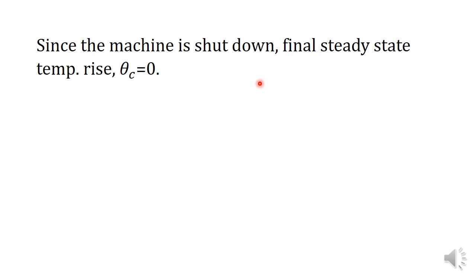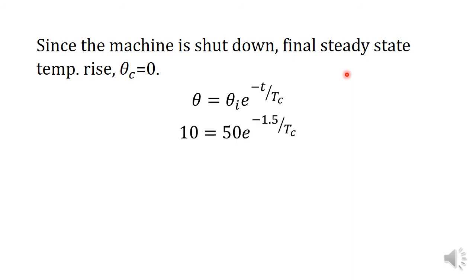Since the machine is shut down and not heated again, it is allowed to cool completely to ambient temperature, so the final steady state temperature rise theta_c equals 0. The cooling equation becomes theta equals theta_i times e raised to minus t by tc. Substituting theta equals 10 degrees Celsius, theta_i equals 50 degrees Celsius, and t equals 1.5 hours, the cooling time constant tc is calculated as 0.932 hours.